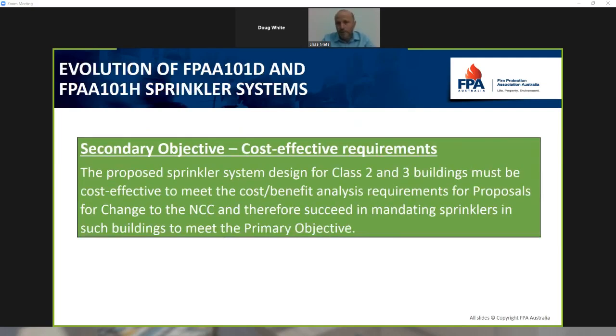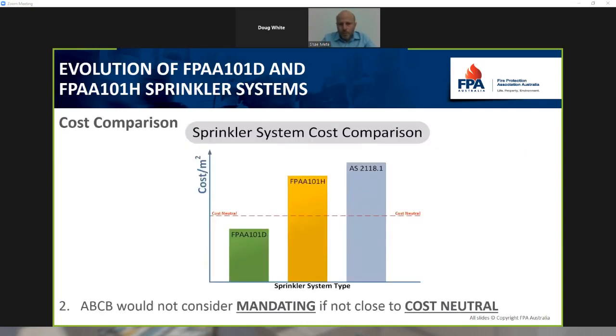The second objective is cost effectiveness. It still comes back to that cost, because if we don't get the cost effectiveness, forget about the primary objective, we're not going to get sprinkler protection in there at all. Through the process and considering costs, we had 2 sprinkler systems, as I said earlier, the 101D system and the 101H system, and you can see how they compare to the existing 2118 suite of systems. This line here represents the cost neutral point. In other words, if you can build a system that's below that line in cost, there's a good chance you'll get it in the code. 101D did that, 101H didn't, and you'll see why a little bit later. But when you consider both of them in the proposal for change, they pretty well balanced out, and we ended up with a very close to cost neutral result, and the ABCB thankfully decided to go ahead and mandate that.